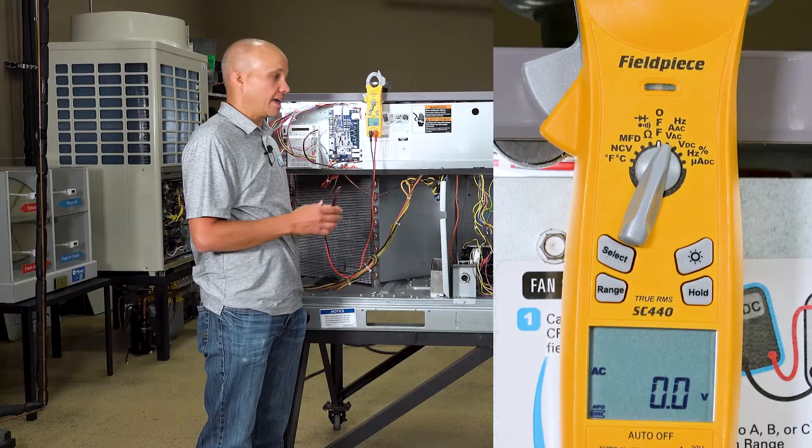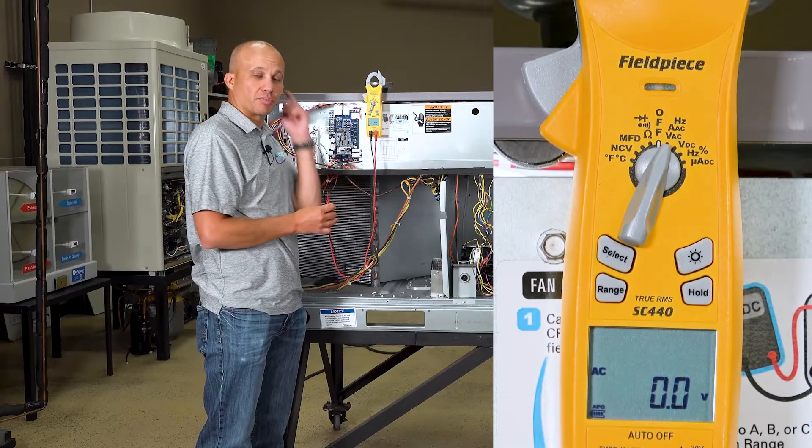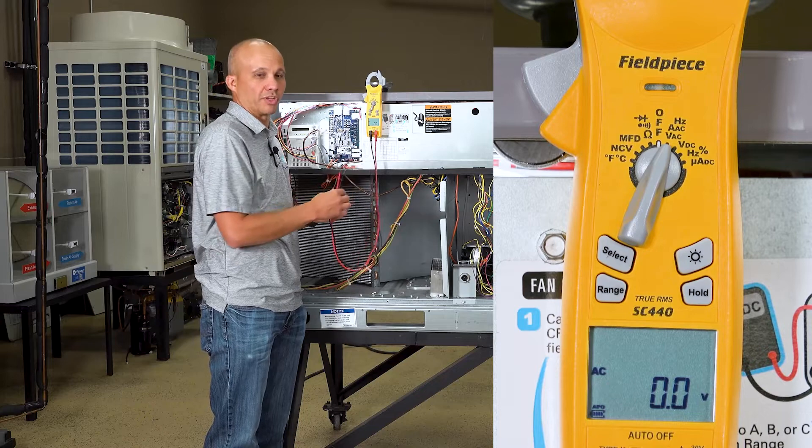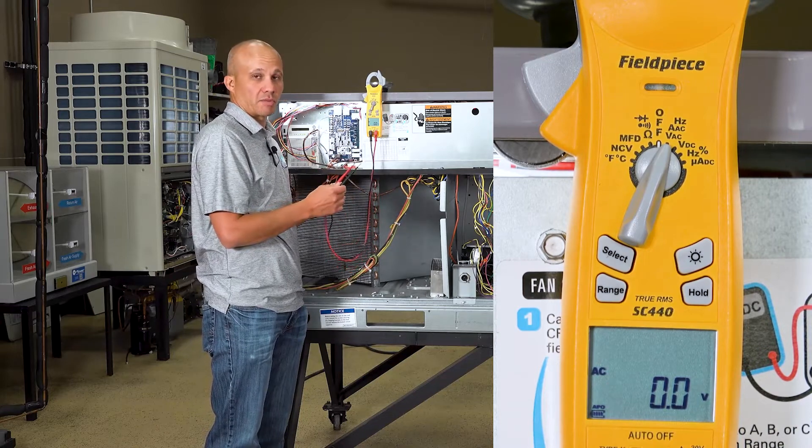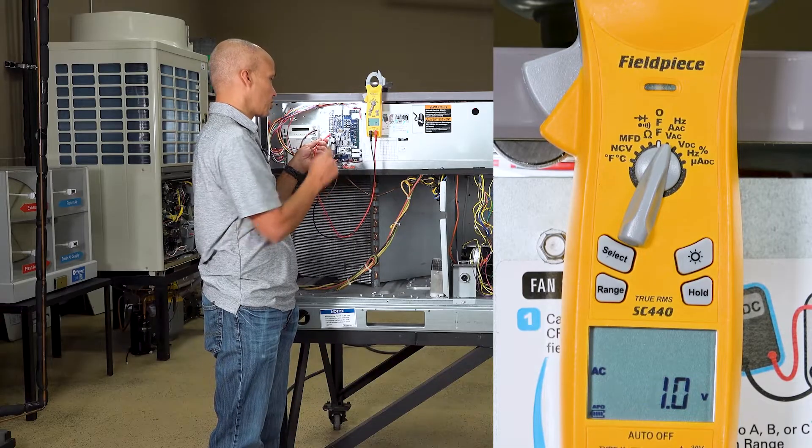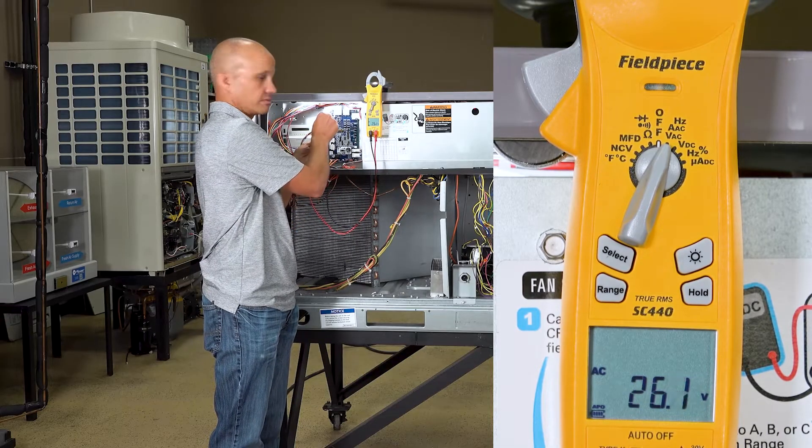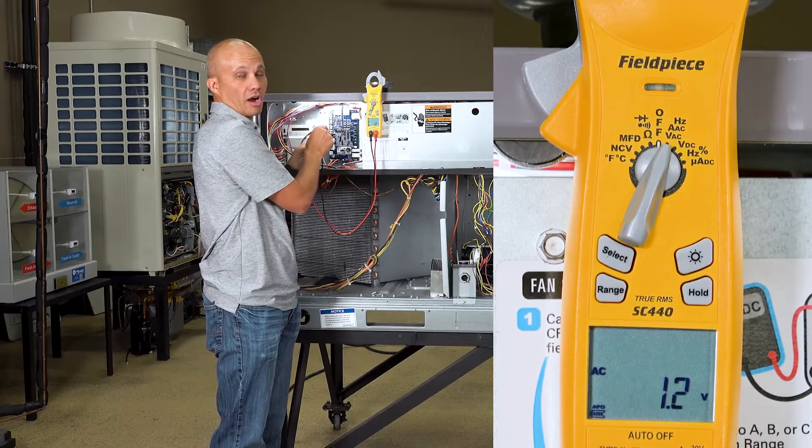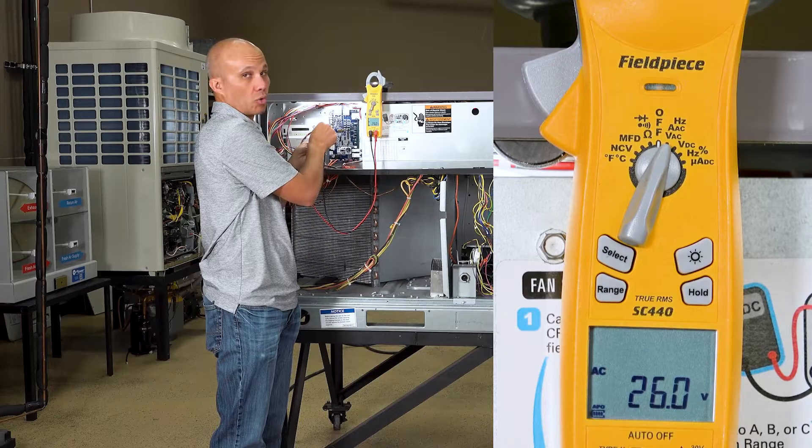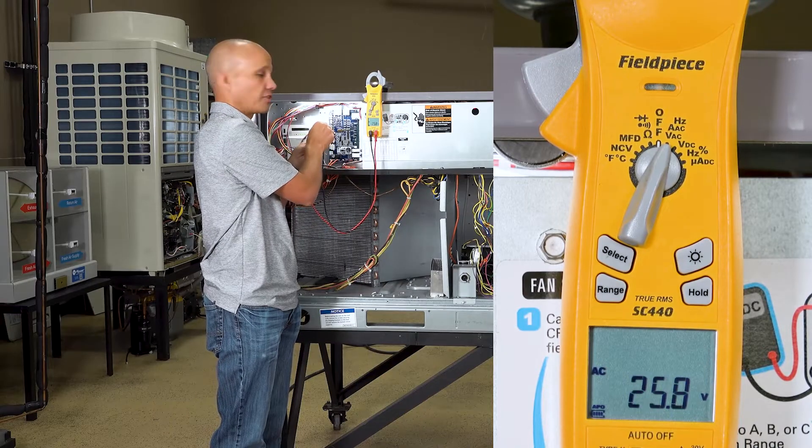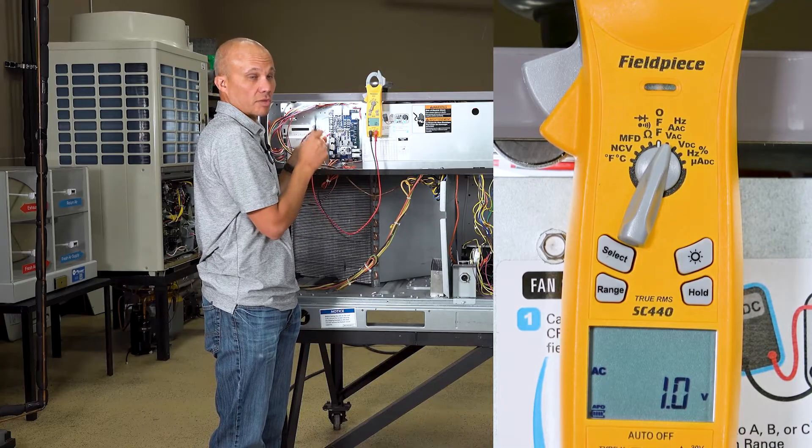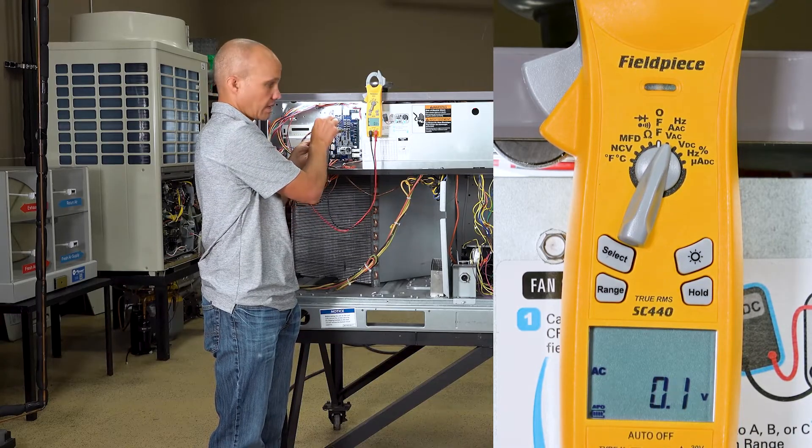Now from the thermostat we have a call for fan. You might be able to hear this fan. This is a pretty quiet unit. It's a vane axial fan instead of belt driven. So it's pretty quiet but you can hopefully hear the fan running. We'll take those same measurements we took a minute ago and see what we got. So I'm going to start with R and C just to make sure we have power which we obviously do. 24 volts, I'm good. When I go to R and Y for cooling, 24 volts because there's no cooling call. R and W for heat, 24 volts, no heating call. Now when I go to R and G there is a call so I'm expecting zero and there is.